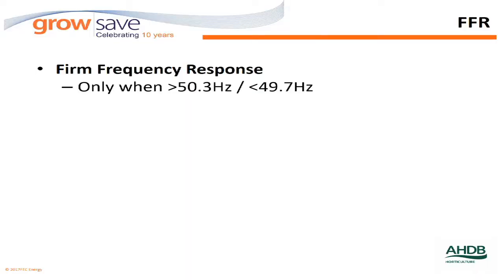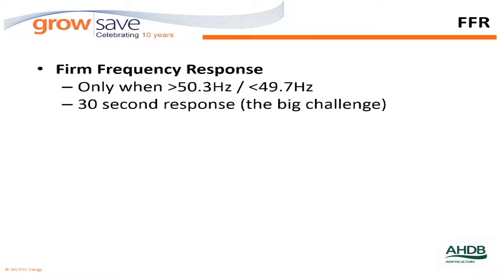It's the bottom end of things that's perhaps of more relevance, particularly to your generators. So yes, if the frequency drops under 49.7, there's a call to run. The challenge here is that whatever your contracted capacity is, you have to be able to deliver that within 30 seconds.